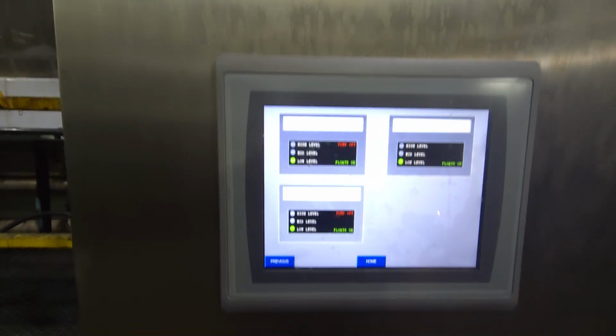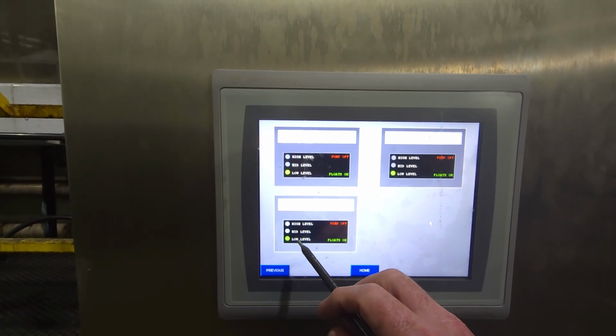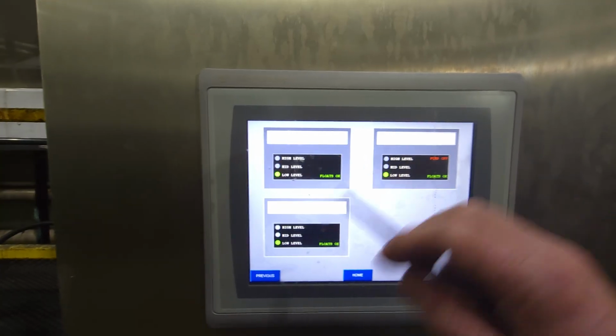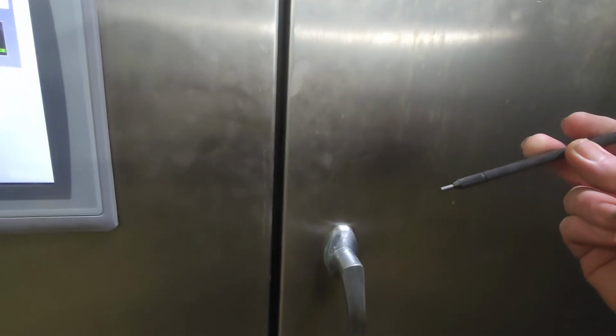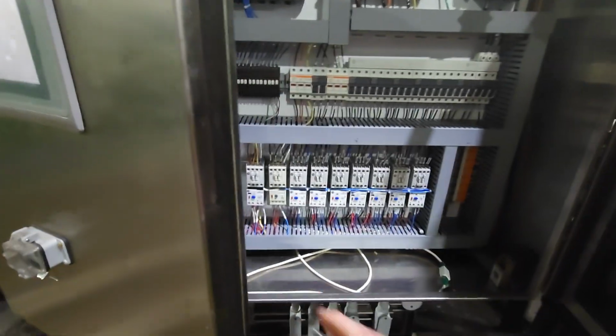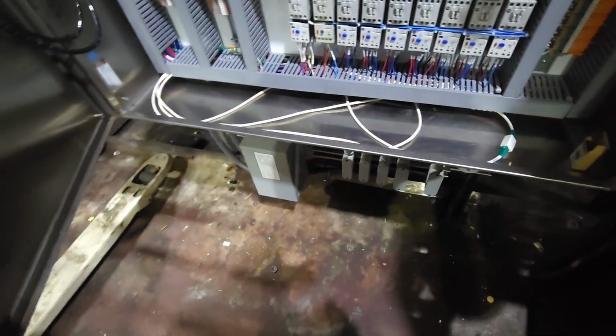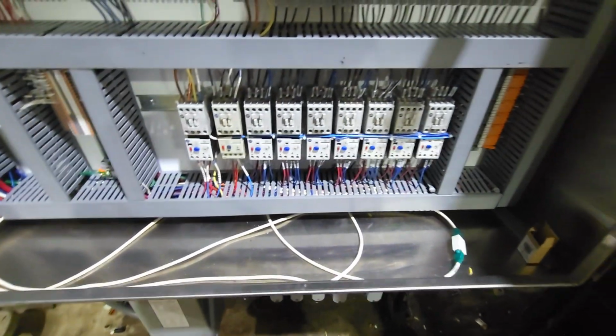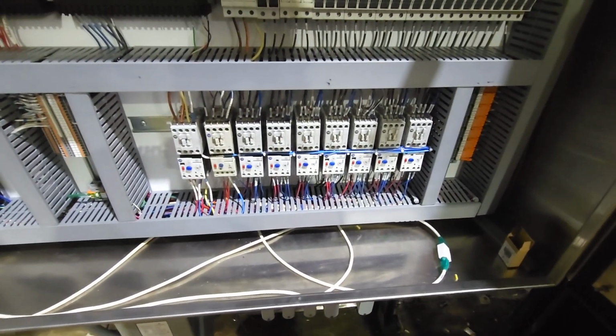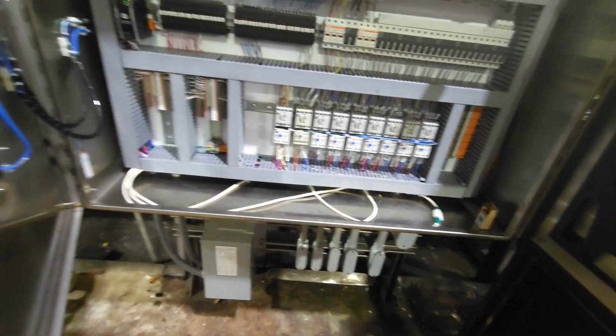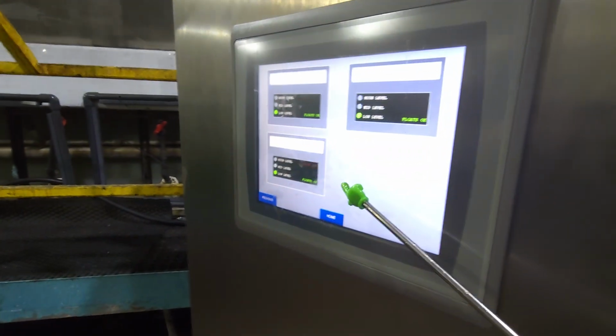Alright, this is the panel for this one. Right here shows you your pumps, where your float's set at, whether you're running. I'm going to open this up. I use a scribe, turn it around backwards to open these. This power is on right now, but it's okay because it's going to be on when you've got to work on it. Alright, here's your setup. Put that away. If you have an overload, it will tell you on this screen right here, OL, overload.